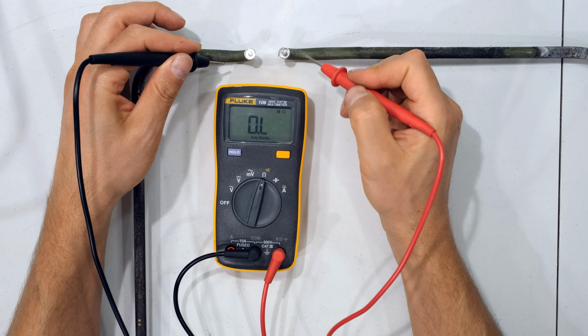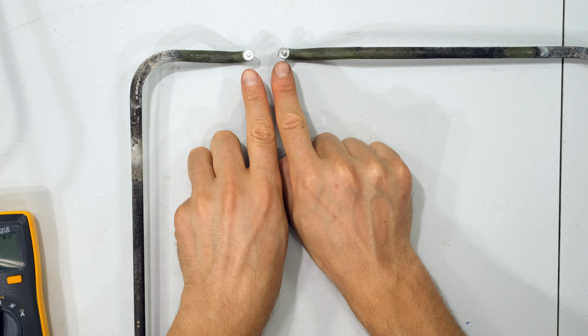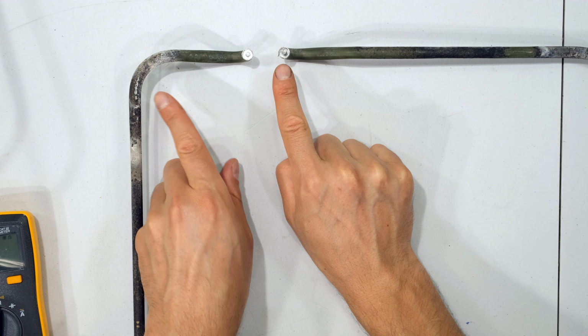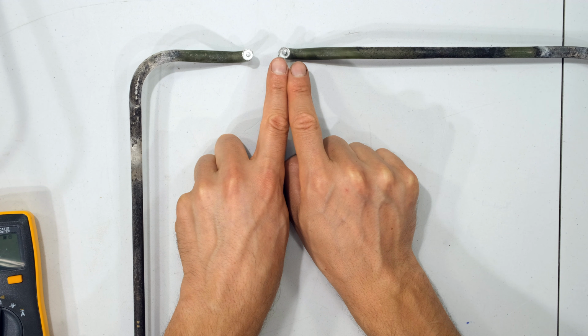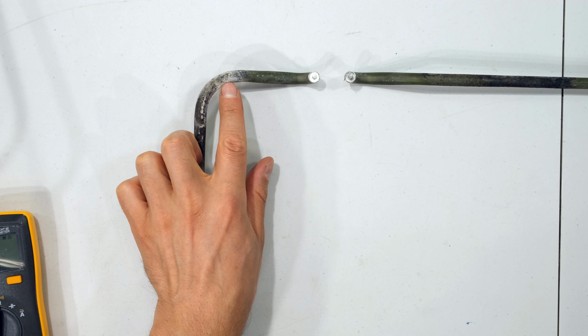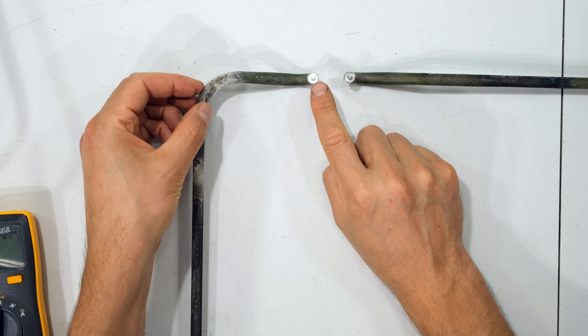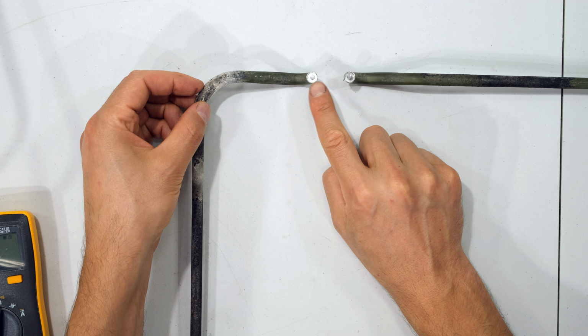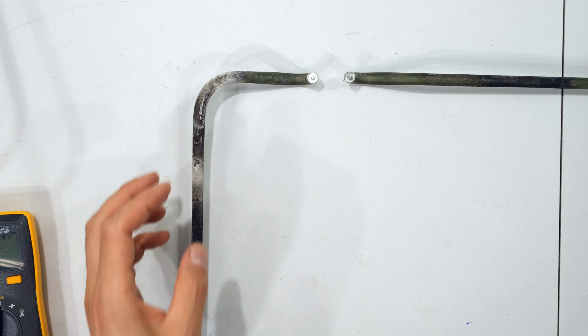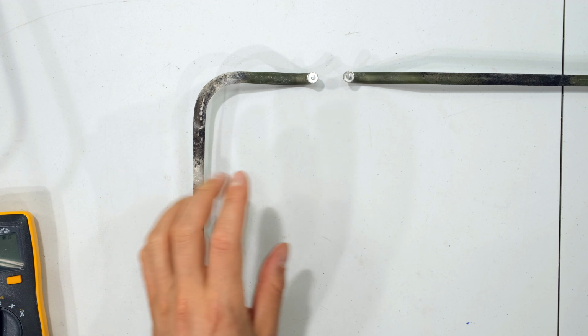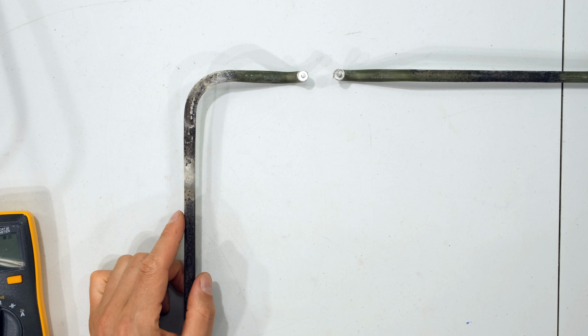I should be getting no resistance here. So that means that somewhere along the path, the electrode inside, the resistive element, has become too close to the steel, or possibly has ionized the insulation and it has reduced the isolation. Therefore, it is now going to trip the earth leakage.